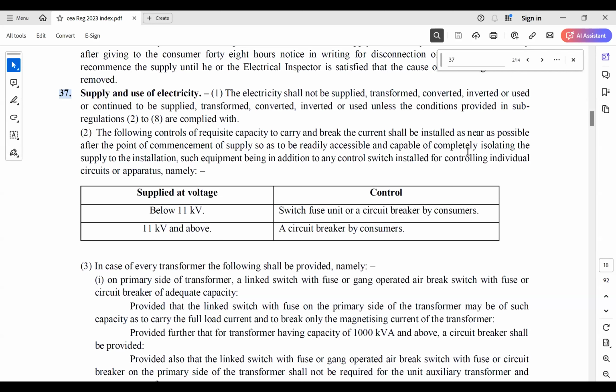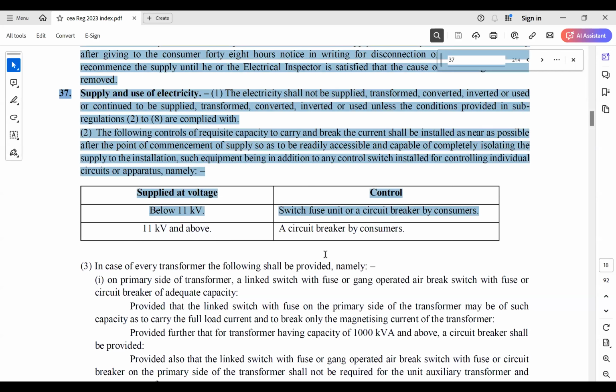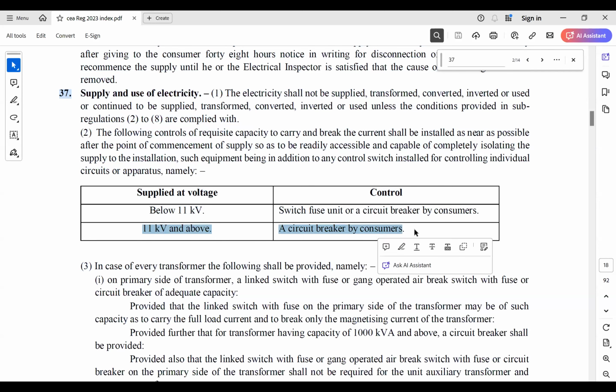when the suppliers supply, say 11 kV supply is coming to a factory industry, as per DISCOM norms nowadays, they have to provide a ring main unit before taking the supply. And the ring main unit encompasses a circuit breaker inside it. And then the supply is fed to the consumer's meter, the HT meter. And after that, earlier it used to be a switch fuse unit or a circuit breaker. Now, by this law, what has happened? The consumer has to provide a circuit breaker at that point. And then the supply is fed to the transformer.